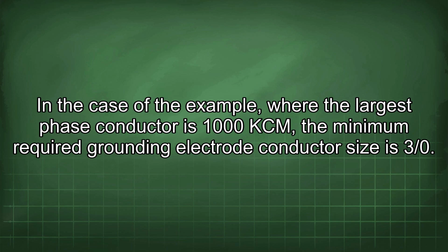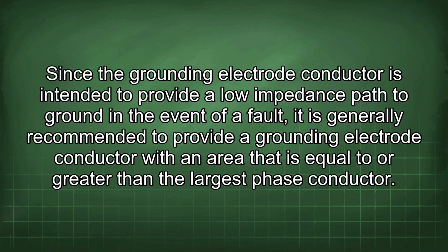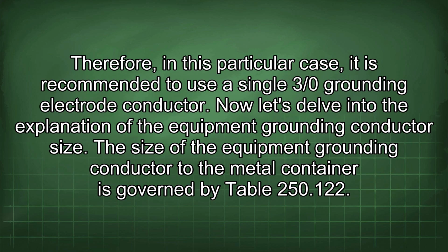size is 3/0. Since the grounding electrode conductor is intended to provide a low impedance path to ground in the event of a fault, it is generally recommended to provide a grounding electrode conductor with an area that is equal to or greater than the largest phase conductor. Therefore, in this particular case, it is recommended to use a single 3/0 grounding electrode conductor.